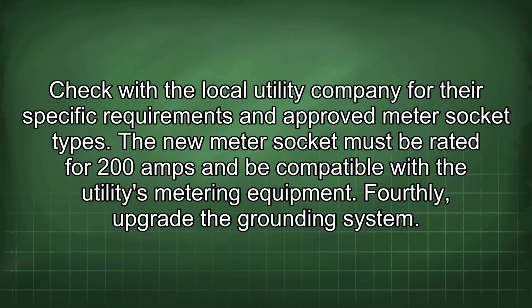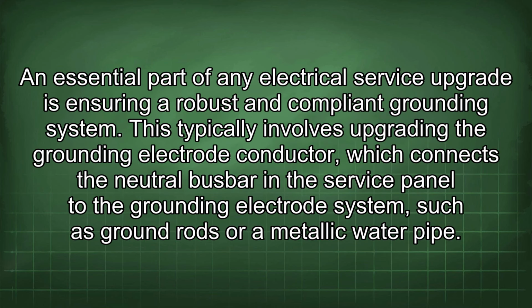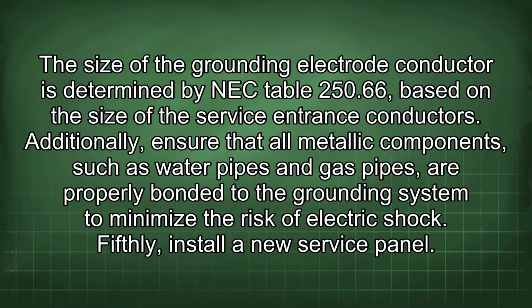Fourthly, upgrade the grounding system. An essential part of any electrical service upgrade is ensuring a robust and compliant grounding system. This typically involves upgrading the grounding electrode conductor, which connects the neutral busbar in the service panel to the grounding electrode system, such as ground rods or a metallic water pipe. The size of the grounding electrode conductor is determined by NEC Table 250.66, based on the size of the service entrance conductors. Additionally, ensure that all metallic components such as water pipes and gas pipes are properly bonded to the grounding system to minimize the risk of electric shock.